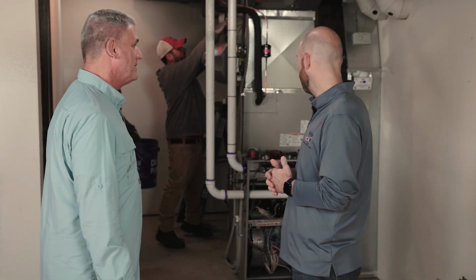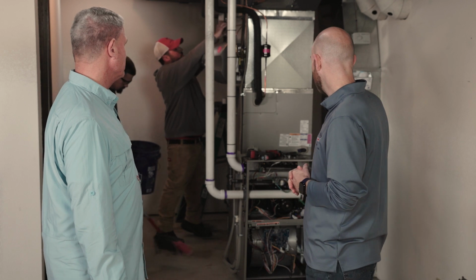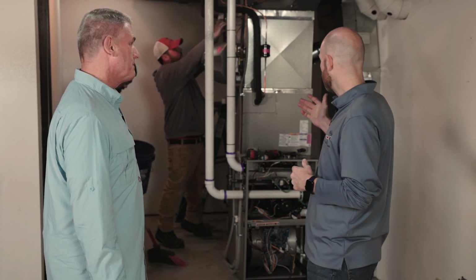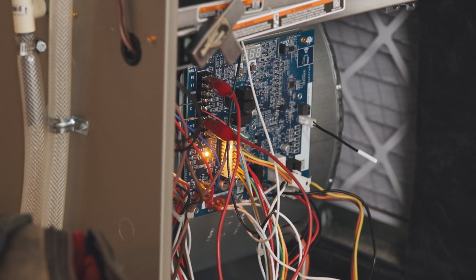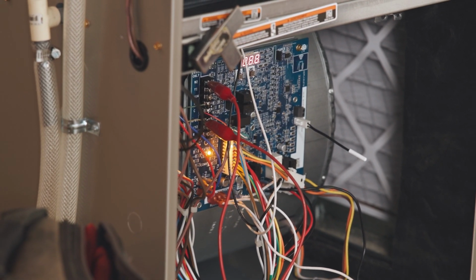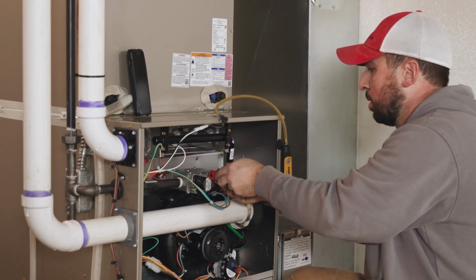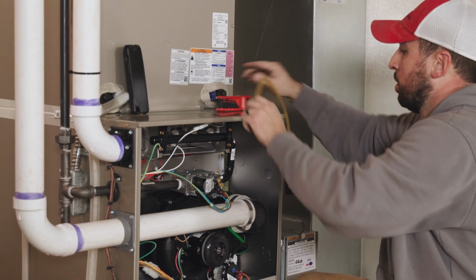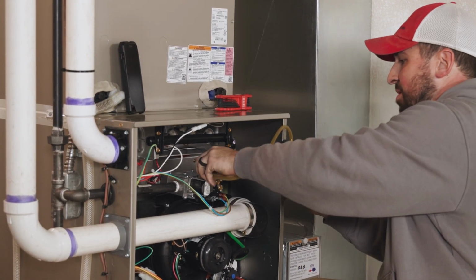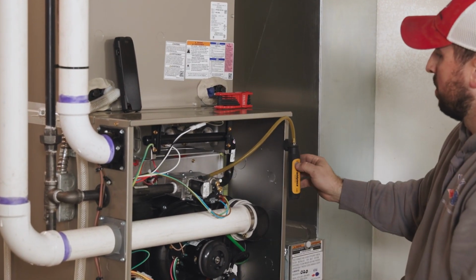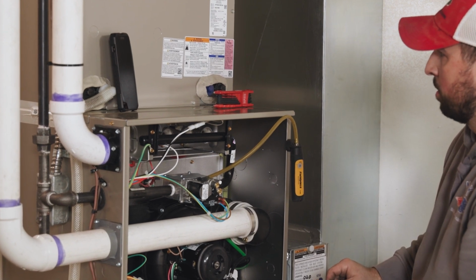The guys are just starting to wrap up and clean up here. Next steps are we're going to turn the power on to the system, give it a call for heating, and then Adam here is going to get down in there and check the gas pressure to make sure it comes on correctly. He's going to check blower speeds, making sure we have the right amount of air flowing through the system.